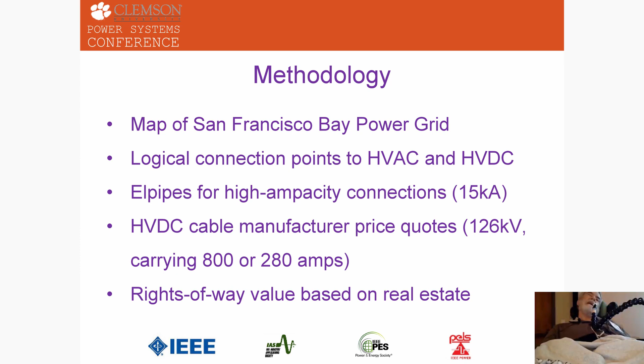This is a map of the San Francisco Bay Area, and all of the nodes I picked are pre-existing large substations. The only part that runs off of established rights-of-way is crossing the Golden Gate Bridge, and there's multiple ways to do that. But those three ampacities cover all of the substations in the area, and by forming a DC loop around the area, you intrinsically have n-1 redundancy, and when you start putting in additional lines, it gets better.